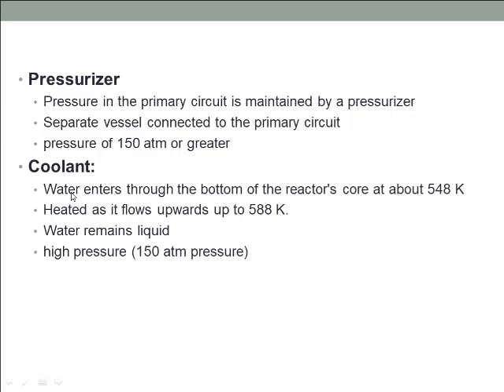The next component is the coolant. Light water is used as the primary coolant in the pressurized water reactor. Water enters through the bottom of the reactor core at about 548 Kelvin and is heated as it flows upward through the reactor core to a temperature of about 588 Kelvin. The water remains in liquid form despite the high temperature due to the high pressure of the primary coolant loop — usually 150 atmospheric pressure is maintained.